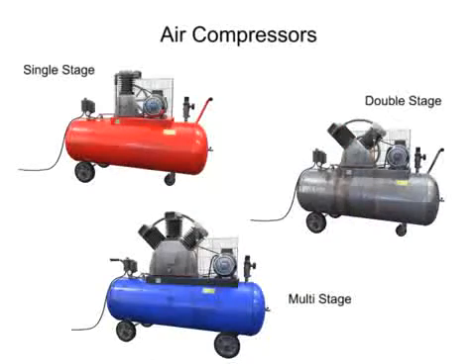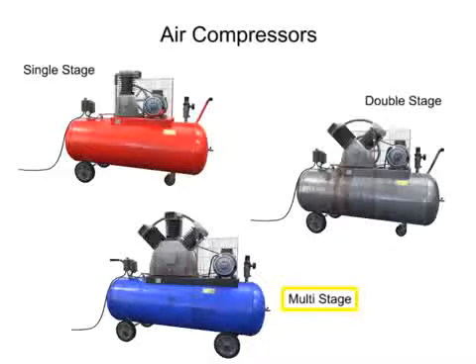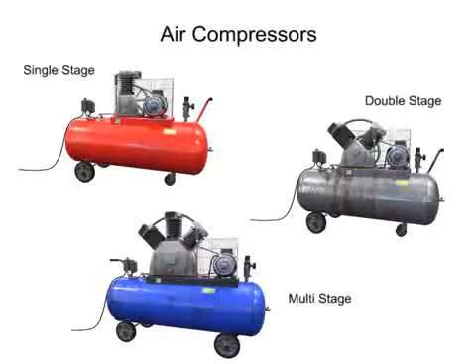If pressures of more than about 175 PSI are needed, multi-stage compressors should be used. On these larger compressors, cooling may take place by circulating water instead of air. To reach a pressure of 2,500 PSI, as many as 6 or 7 stages may be needed with cooling between each stage. Their versatility makes compressors one of the primary components in air production.